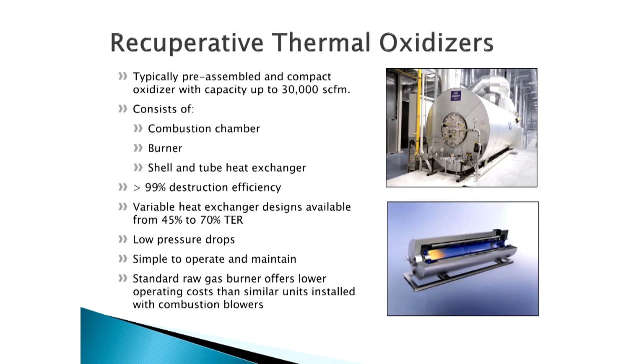We have burners that we can deploy depending on what we're trying to achieve on the back end of the device. That may have dilution air, or they may not have dilution air. We may be trying to achieve very, very low NOx levels with these devices as well. So it really depends on the state we're working in and what the regulatory requirements are as to how we would tailor this type of system.